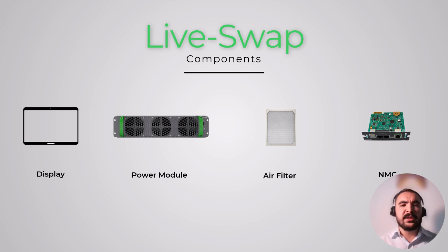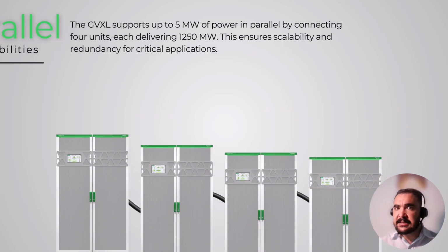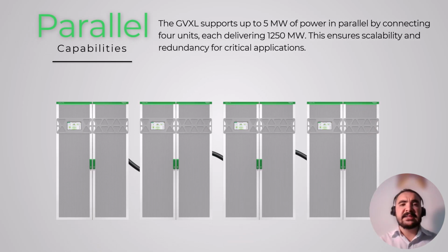Moving on to the parallel capabilities. The Galaxy VXL UPS is capable of handling up to 5 megawatt of power in parallel, or 5 megawatt N plus 1 in parallel. You can connect only up to 4 units. Each of these units is rated at 1250 kilowatt of power. And a fun fact, if you add this up, the total 5 megawatt setup would span 5 meters in width. Just imagine it. 5 meters for only 1.5 megawatt, or 5 meters for 5 megawatt setup.